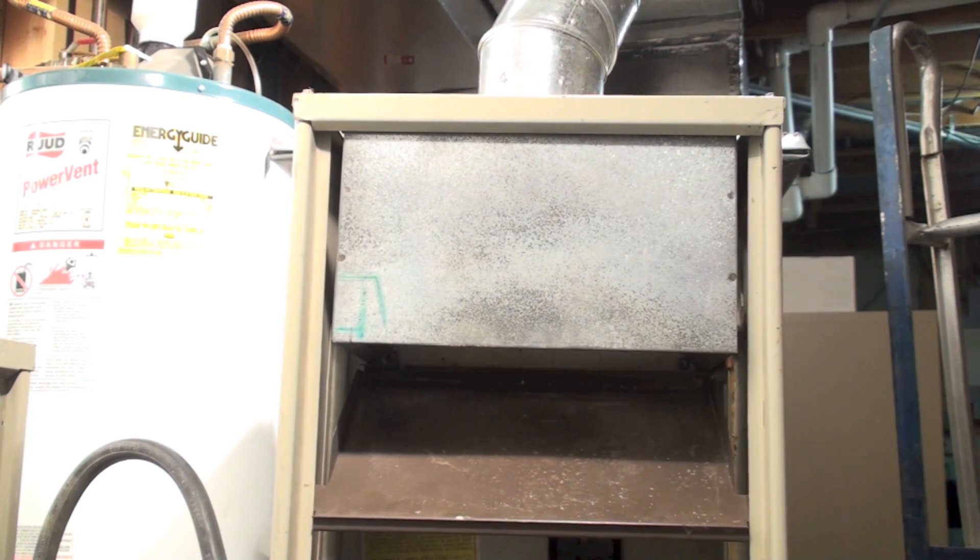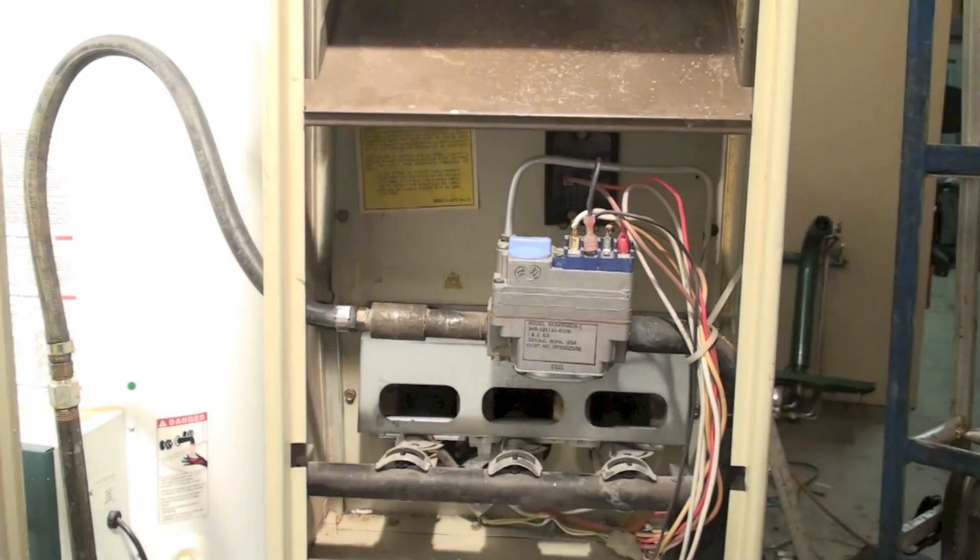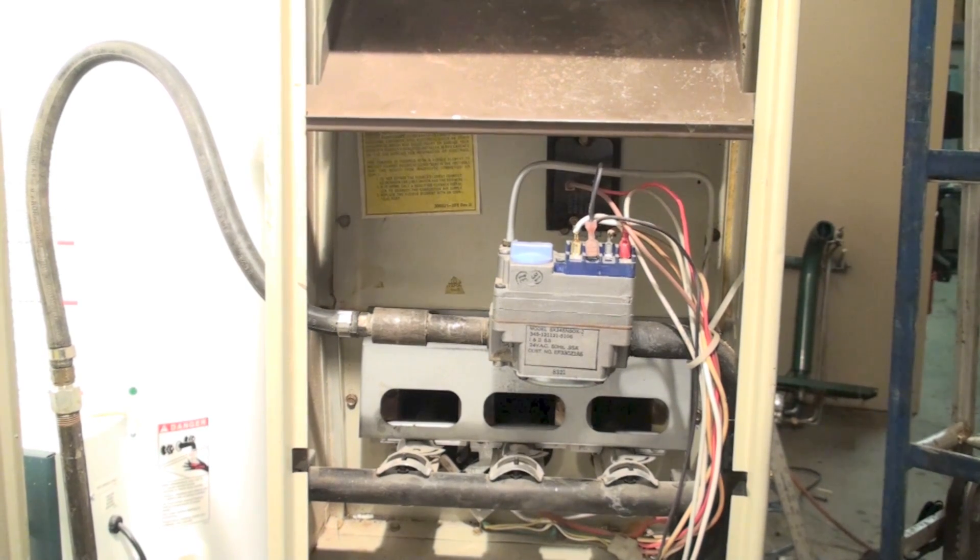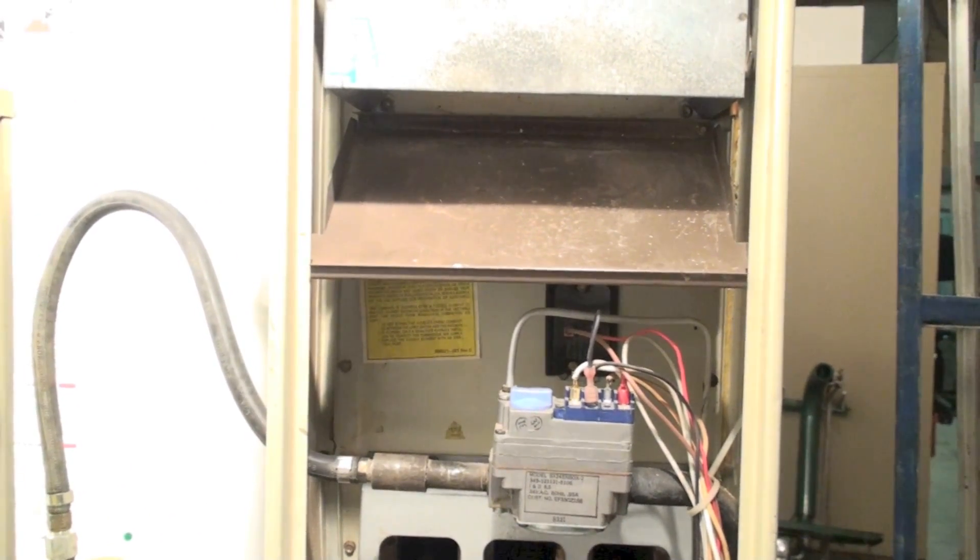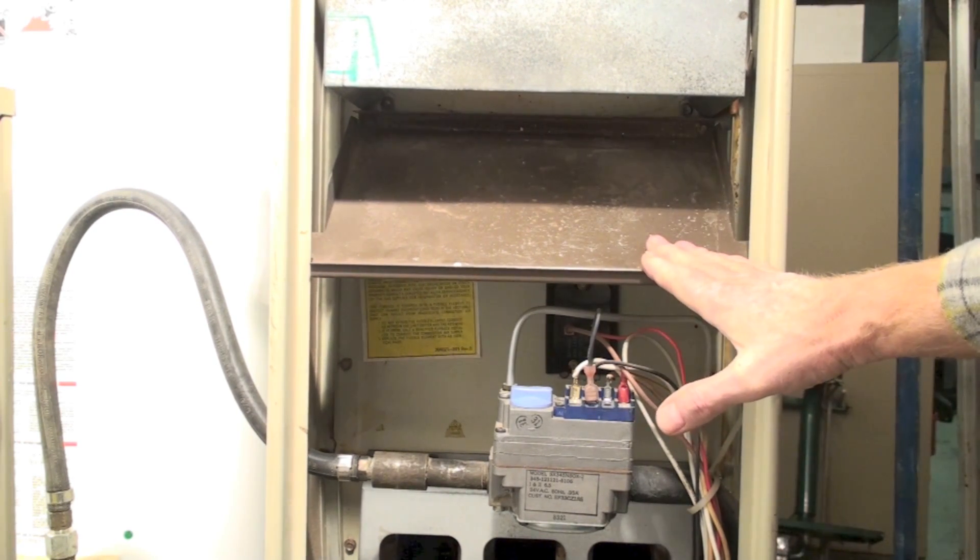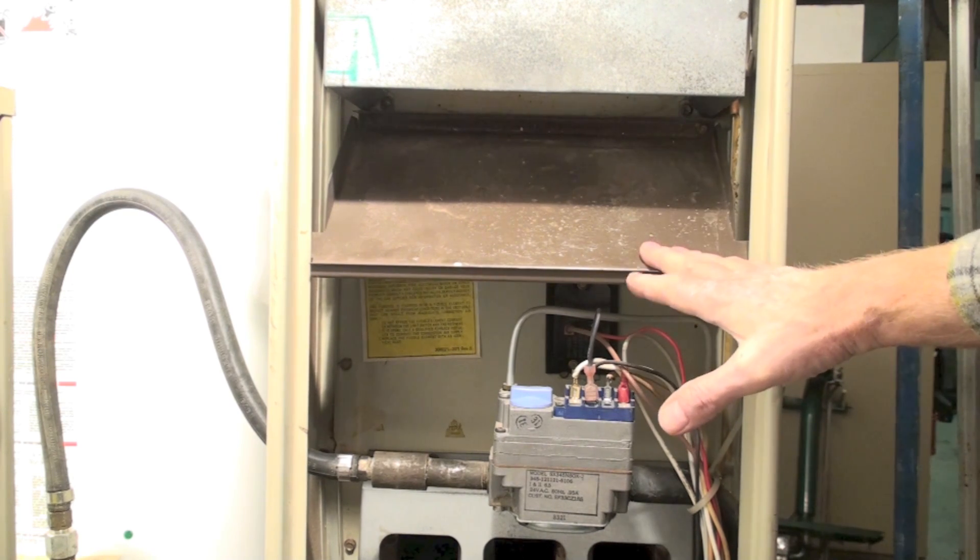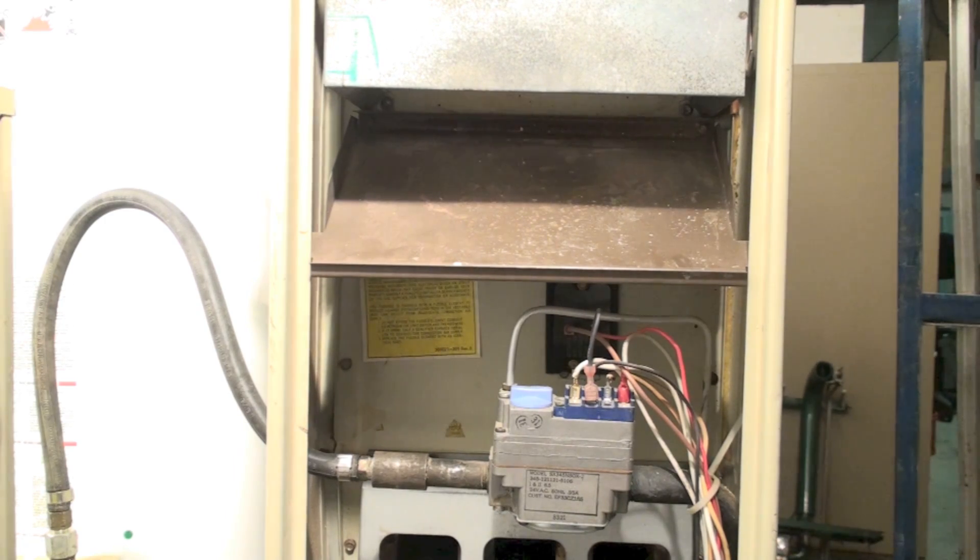That was not a real accurate way. It's true that if it was just steady state operating, it would come up to those specs. However, there were parts of this furnace that were not efficient. The draft hood here drew air out of the house all day long, so that's heated air, so you'd lose that.